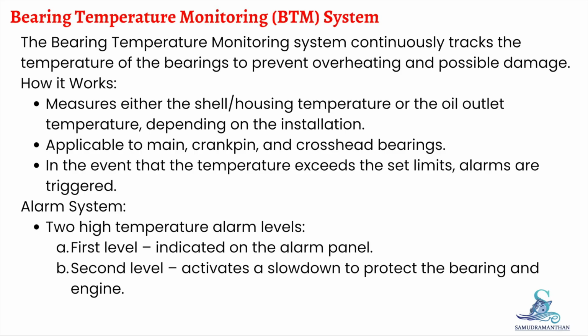Bearing Temperature Monitoring System, BTM. Next, we have the Bearing Temperature Monitoring System, which focuses on preventing overheating and thermal damage. This system can monitor either the shell or housing temperature, or the oil outlet temperature, depending on the installation. It can be fitted to main bearings, crankpin bearings, and crosshead bearings, and optionally even to moment compensators. If the temperature exceeds set limits, the system triggers its alarms.